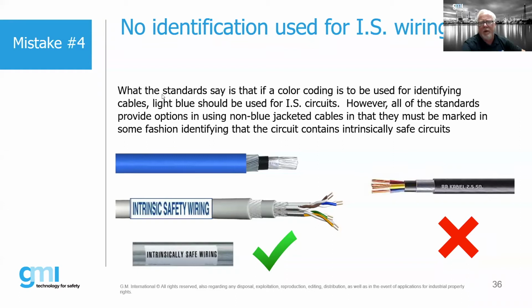No, the point is, we supply products as well, and people are saying, we have to have light blue cable. And I'm usually asking, is this for intrinsic safety? Yes. Why do you need light blue? Because it's mandated. Is it mandated by a customer? No, we're following the relevant standard. Are you using the color blue for your indication of all IS? Yes. Well, in a pinch, the standards do allow you to use other methods to indicate your wiring, and you do not necessarily have to use light blue cabling. It's good practice, and I don't want to discourage anybody from doing that. However, all the standards basically allow you the option to do something else.